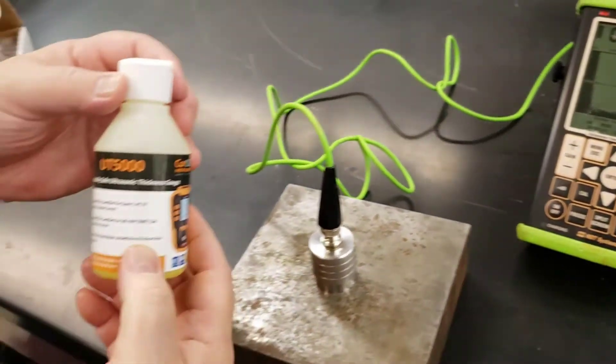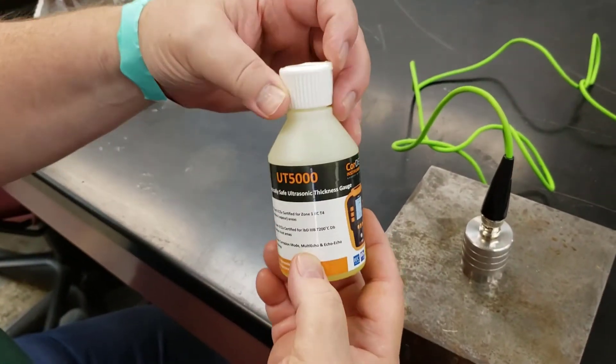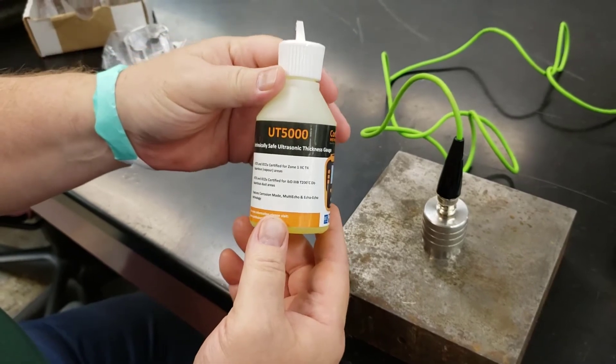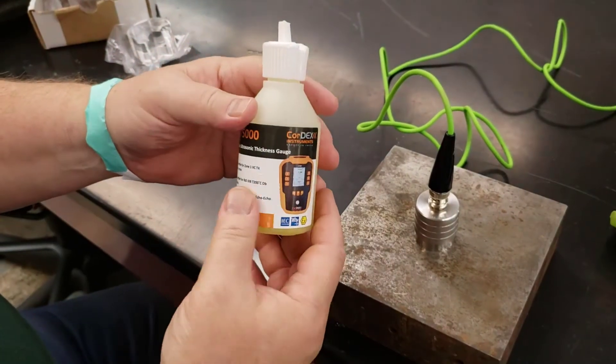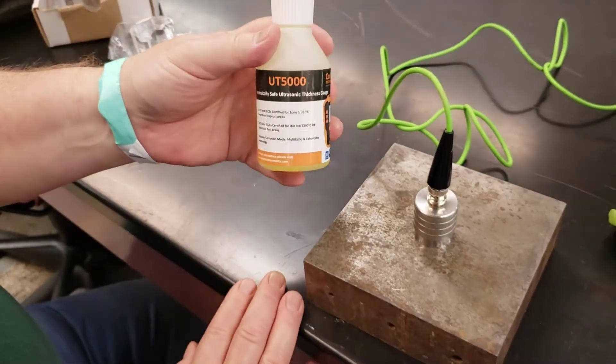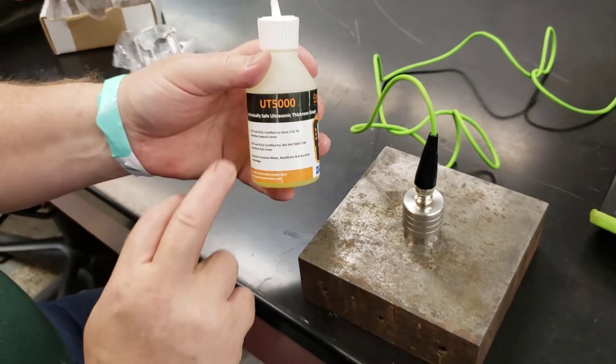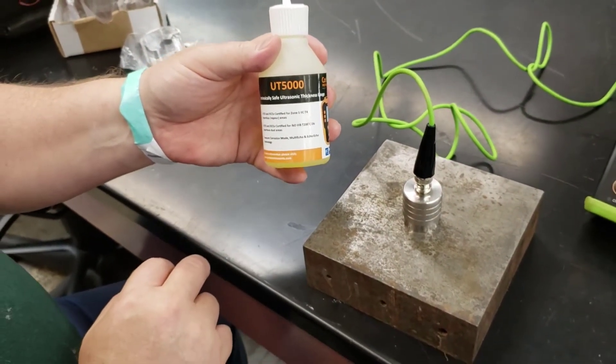We need to use some contact fluid. This can be as simple as Vaseline, but usually we use something a little bit better. If you've ever had an ultrasound in the hospital, it's this material, only a little more sterile. It just has some alcohol in it.